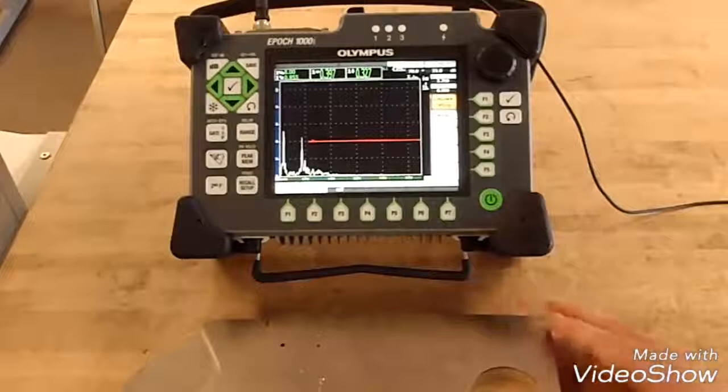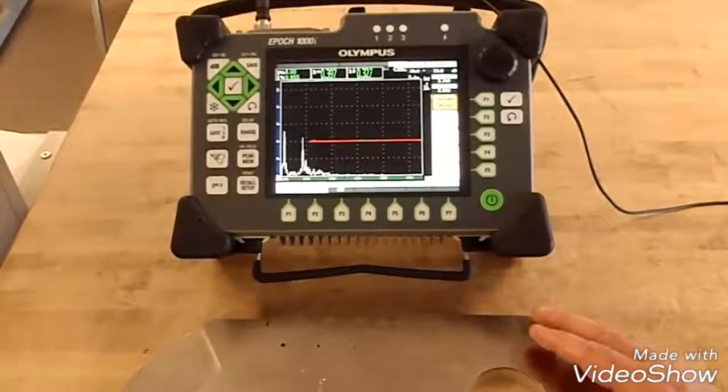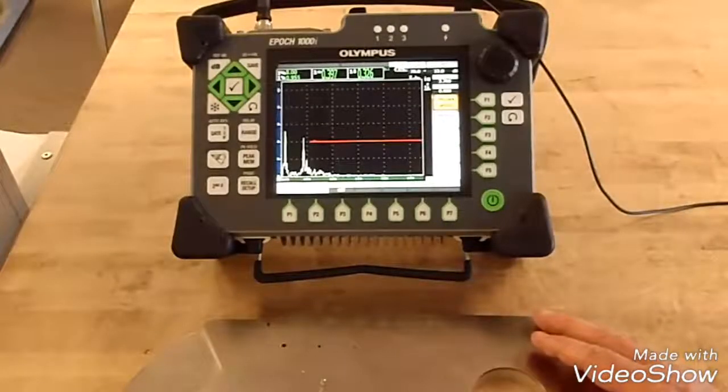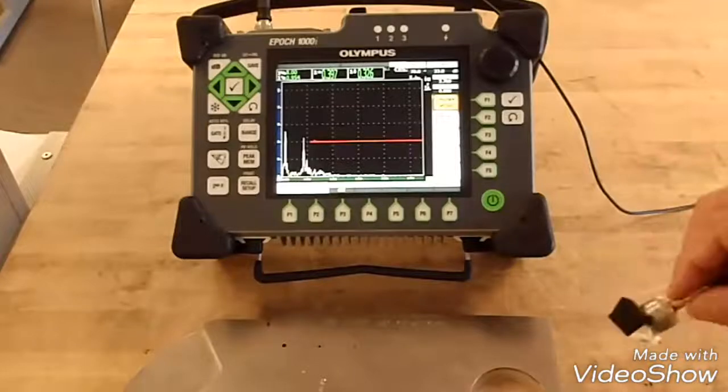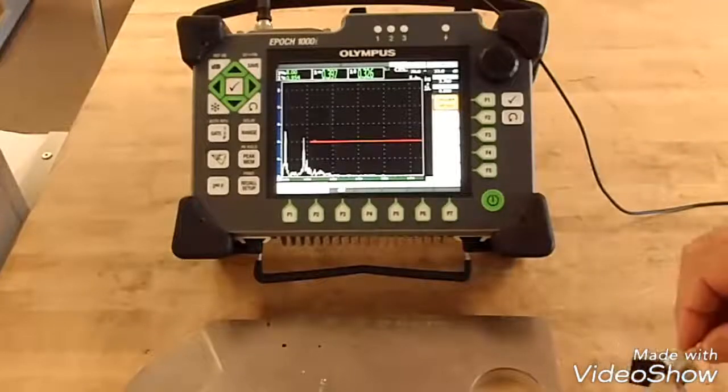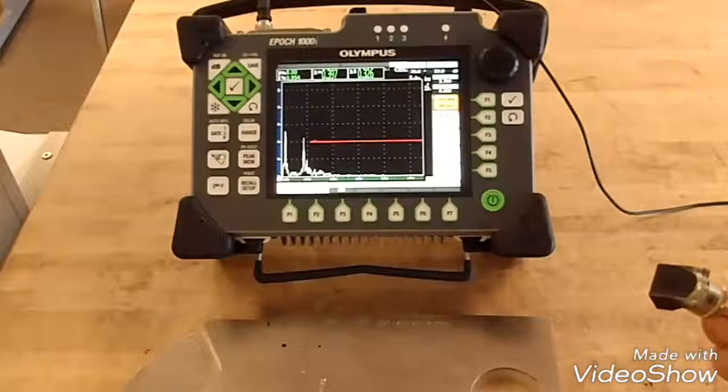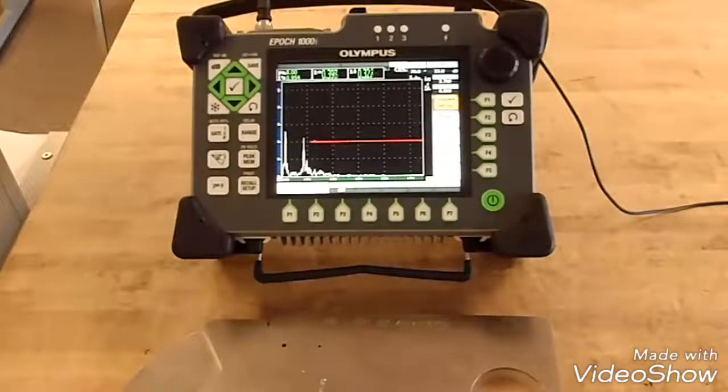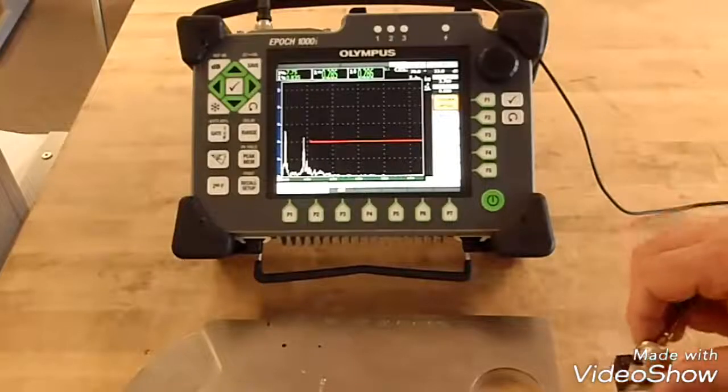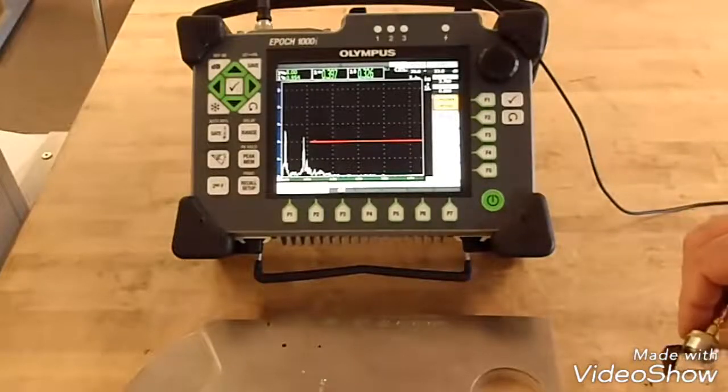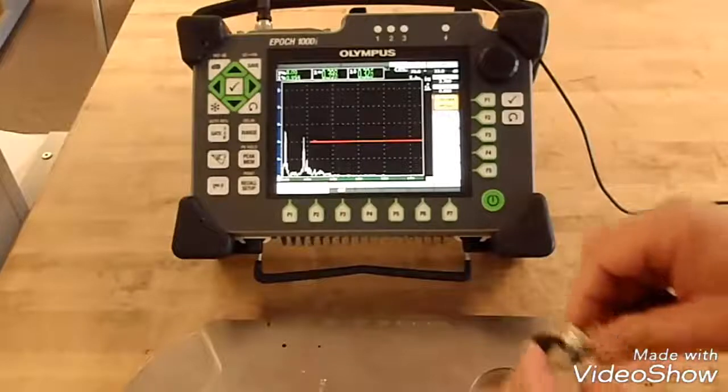Today we're going to calibrate the Olympus EPOCH 1000i for an angle beam test using a two and a quarter megahertz half inch transducer with a 45 degree carbon steel wedge. Before you calibrate, make sure that you couple your transducer to your wedge.